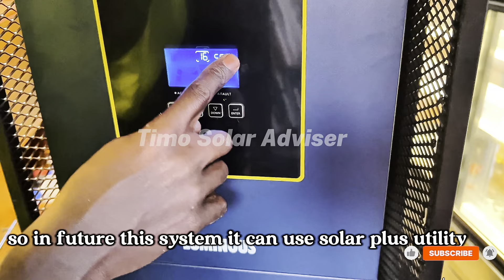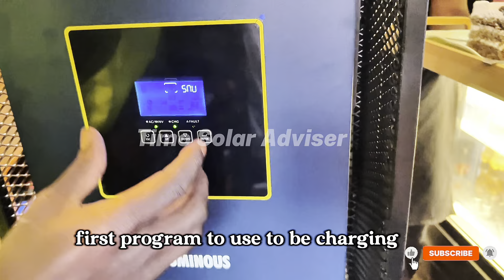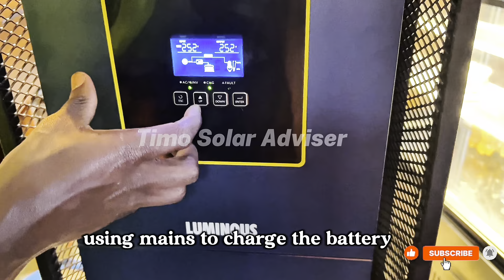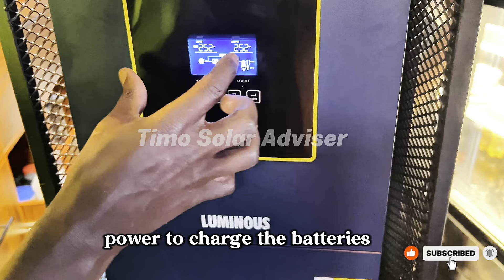Then it is going to be using only solar and the utility. In the future, this system can use solar plus utility. So we just program which is the first source to use for charging. Right now we are only going to use the mains, or what we call the grid, to charge the batteries, because right now this inverter is using mains to charge the battery. As you see, it is using AC from the main supplies. That's why it is using mains power to charge the batteries plus giving power to the loads. Okay. So right now the entire cafe is working properly.